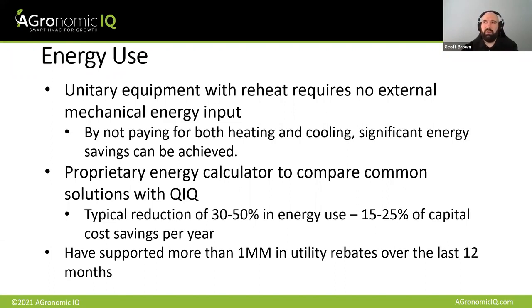And again, as this market matures, it's really important to ensure that we stay compliant with some of the existing rules that are currently not being enforced. One example: there's been a DOE rule on the books for a long time that says you can't pay for both heating and cooling BTUs in the same space at the same time. Again, this rule is largely ignored, but the last count I saw, which was a 2019 number, showed that indoor cannabis facilities in North America accounted for something like 3.5% of North America's energy use. I suspect that number is quite a bit larger today.